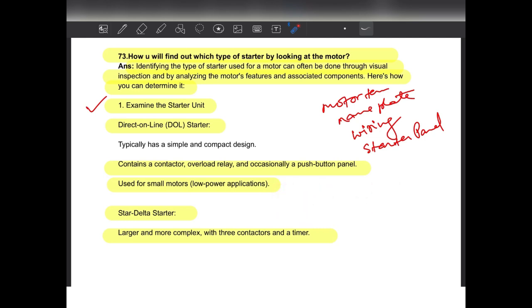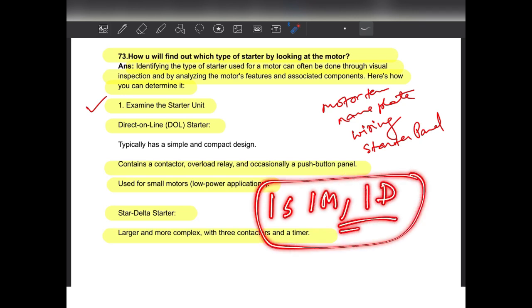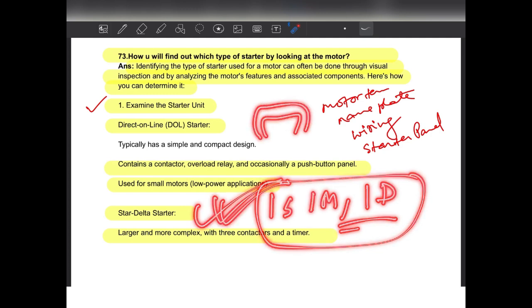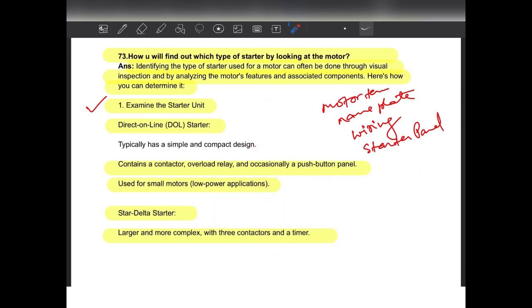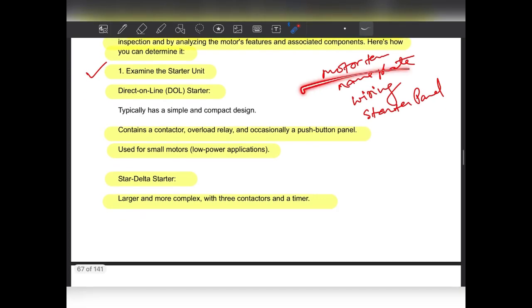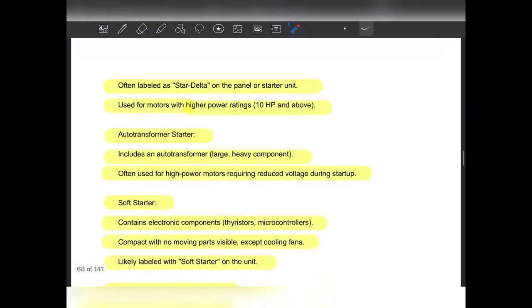Because star delta needs one timer, one star contactor, one main contactor, and one delta contactor, and interlocking also. So you can easily understand star and delta. In star, we short the terminals of the power winding. So you look at this, and you can also find out which type of winding is there with the help of the nameplate.